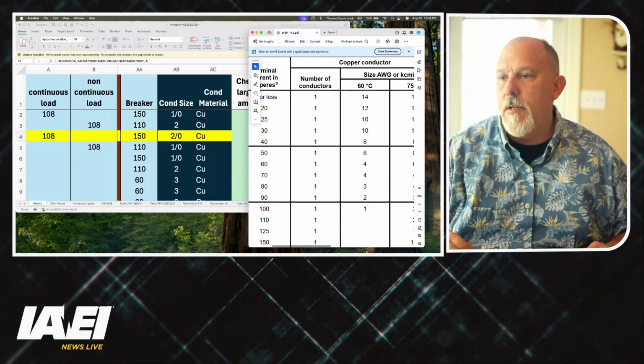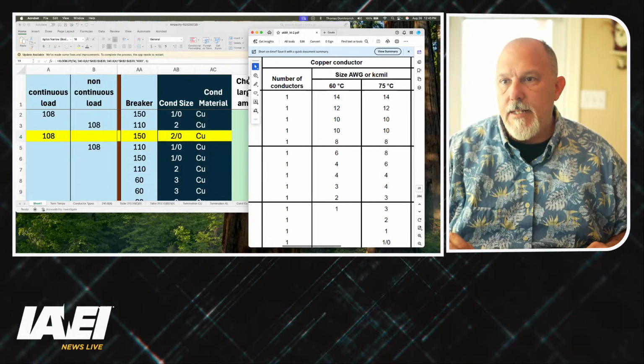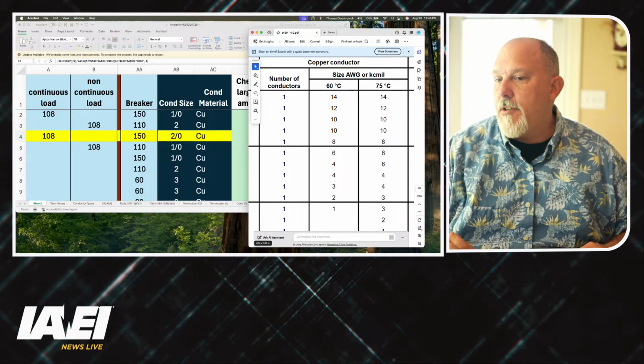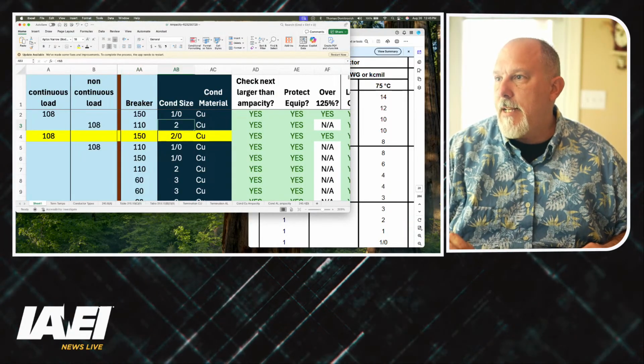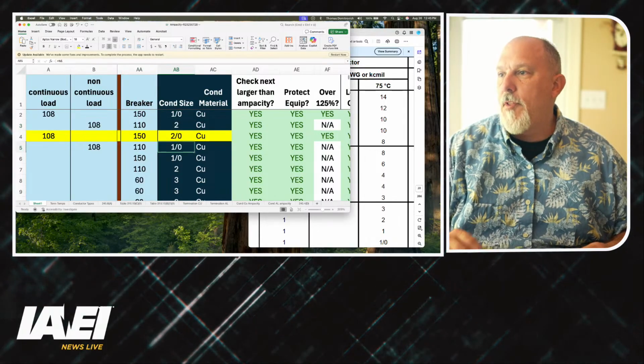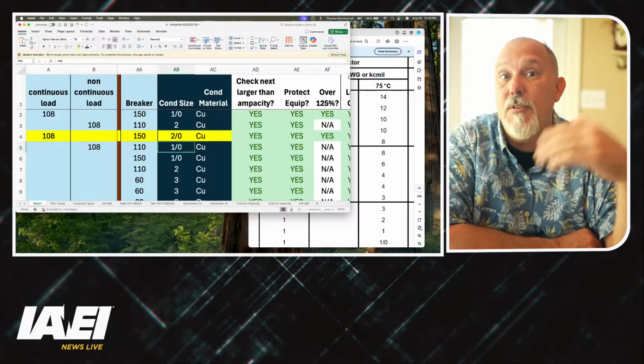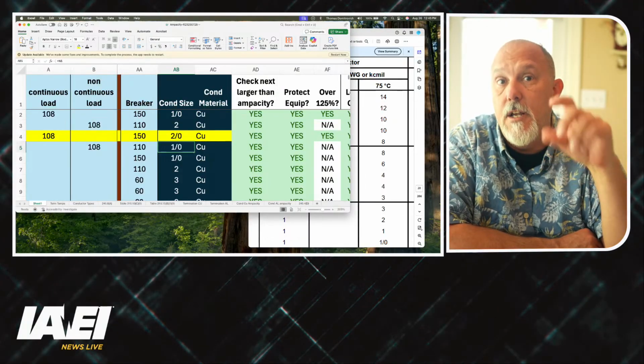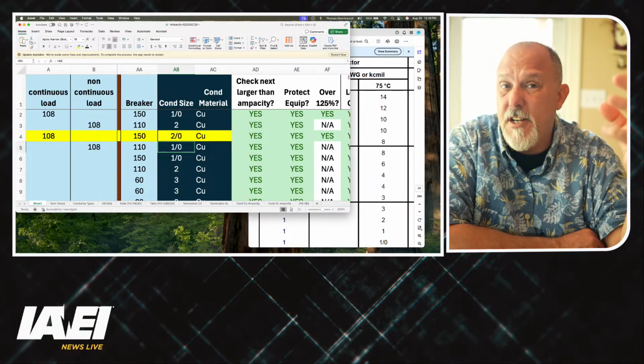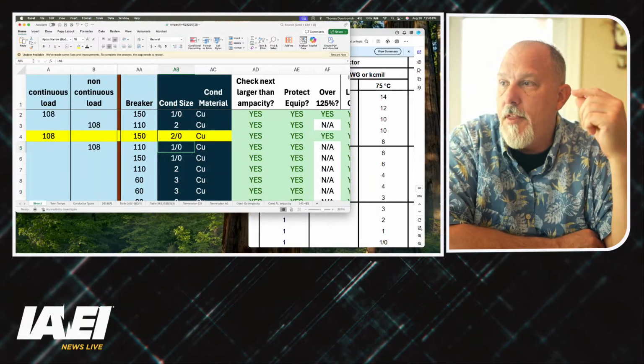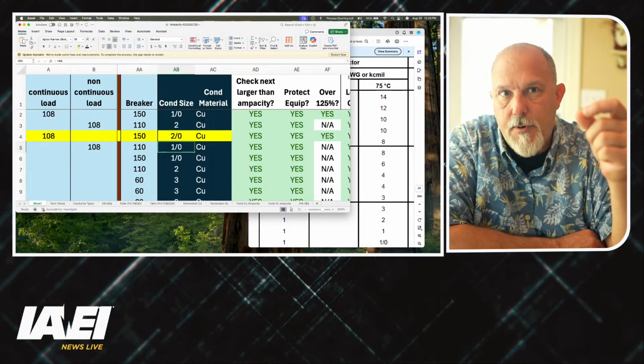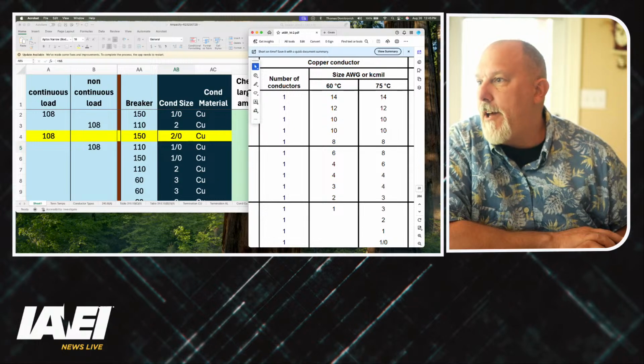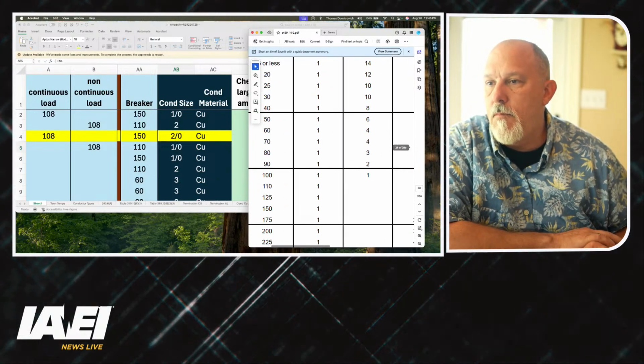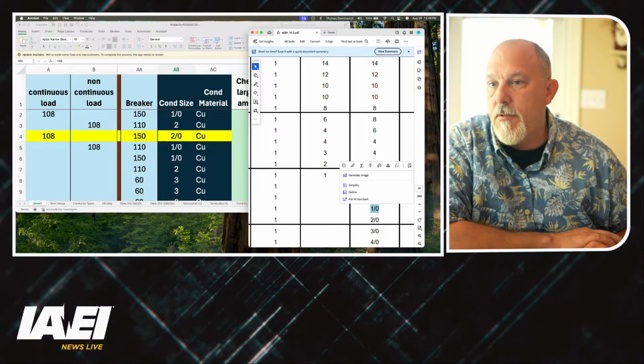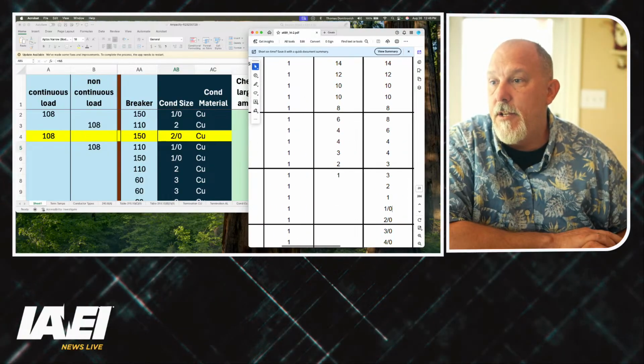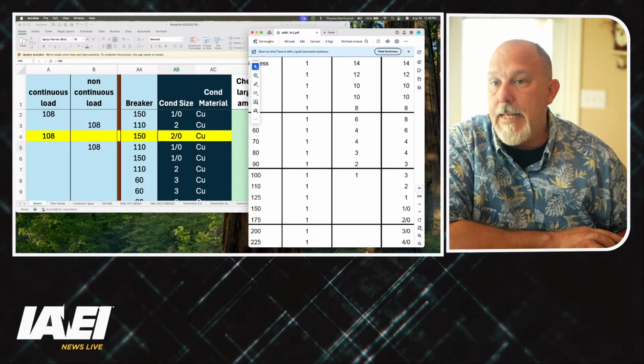You see that at the bottom? A 110 amp breaker is tested with a 2 gauge. A 110 amp breaker with a 1/0 is a larger conductor. I can always go larger than a 2 gauge as long as the lugs will let me, because a larger conductor is going to wick off more heat. So the smallest I can go with a 110 amp breaker is a 2 gauge. And for a 150 amp breaker, the smallest conductor I can use is a 1/0.